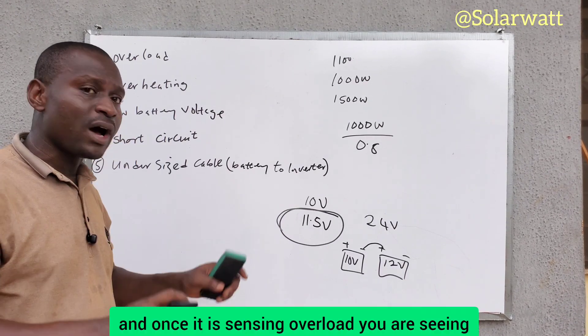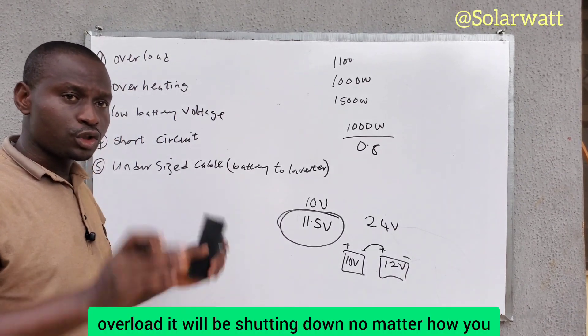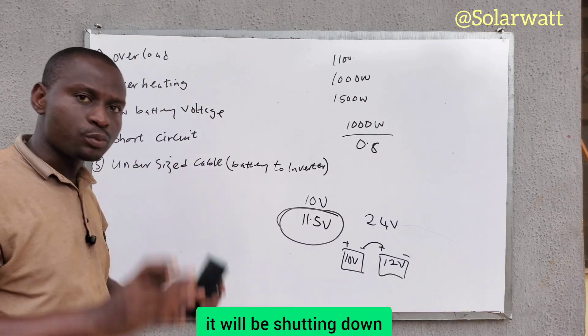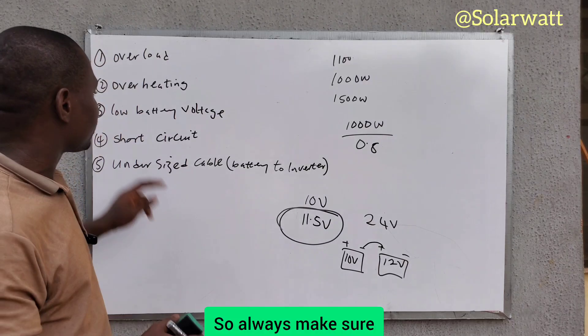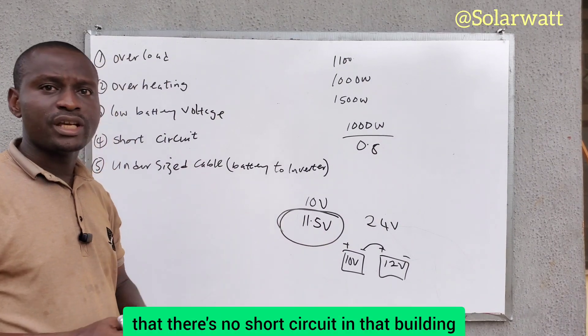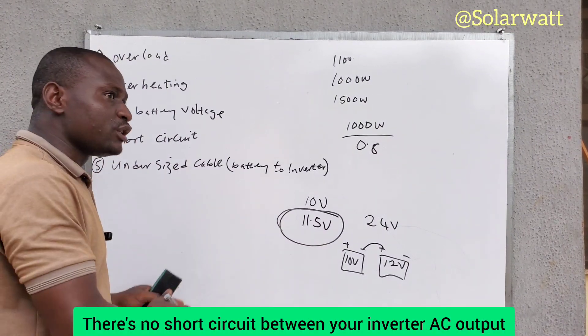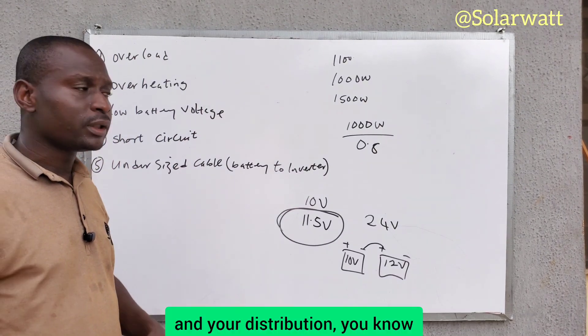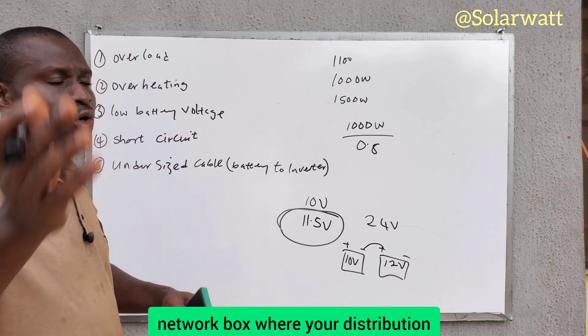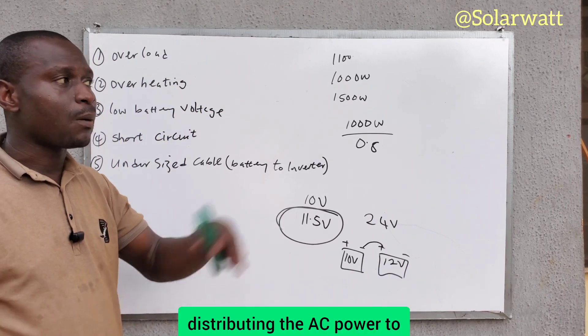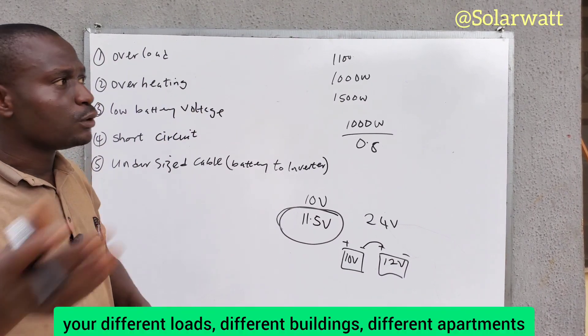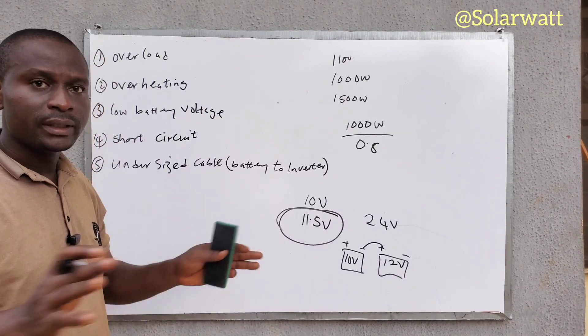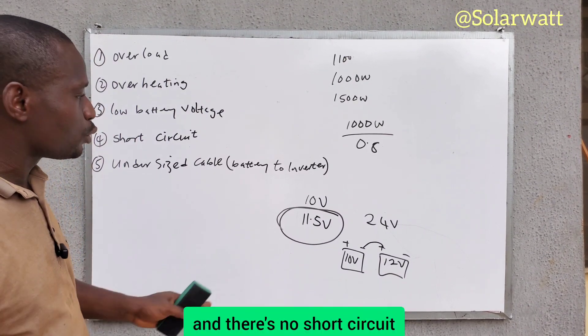Once the inverter is sensing overload and showing overload, it will shut down no matter how many times you restart it. Check the circuit breakers, fuses, and distribution box in the building to ensure there is no short circuit, because short circuit causes the inverter to detect overload. Always make sure there is no short circuit in the building or between your inverter AC output and the distribution network supplying AC power to your different loads and apartments. Confirm the circuit is okay and there is no short circuit.